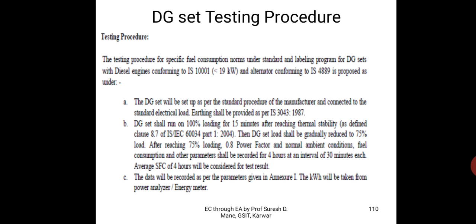DG set is run at 100% loading for 15 minutes to reach thermal stability, then reduced to 75% loading, 0.8 power factor, and all fuel consumption and other parameters are recorded for 4 hours at an interval of 30 minutes each. The average SFC of 4 hours is considered for the test results. It is not like our lab experiments where we take 5 readings over 3 hours and finish it off. Now for every 4 hours average we take 1 reading.